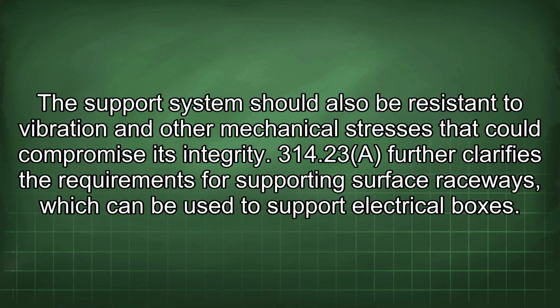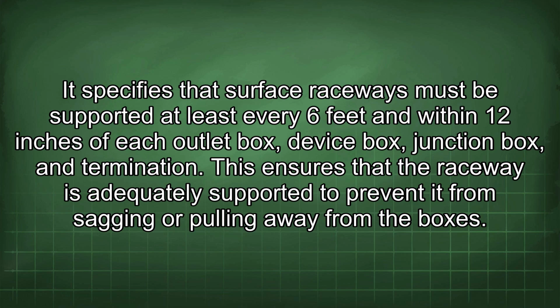314.23 further clarifies the requirements for supporting surface raceways, which can be used to support electrical boxes. It specifies that surface raceways must be supported at least every 6 feet and within 12 inches of each outlet box, device box, junction box, and termination. This ensures that the raceway is adequately supported to prevent it from sagging or pulling away from the boxes.